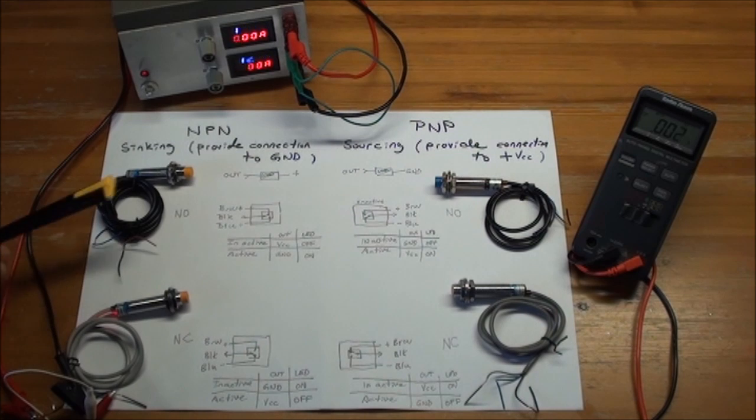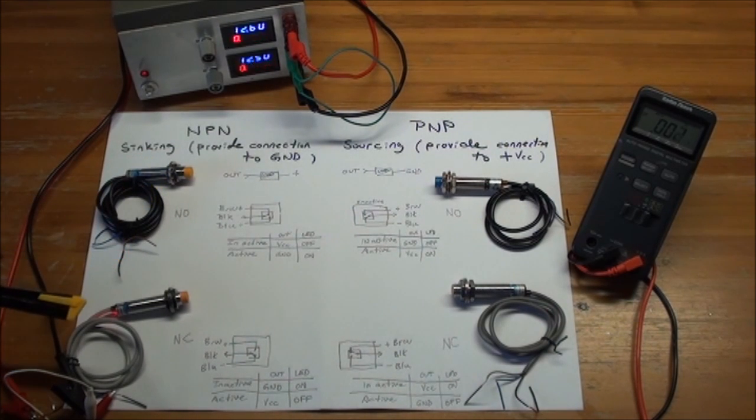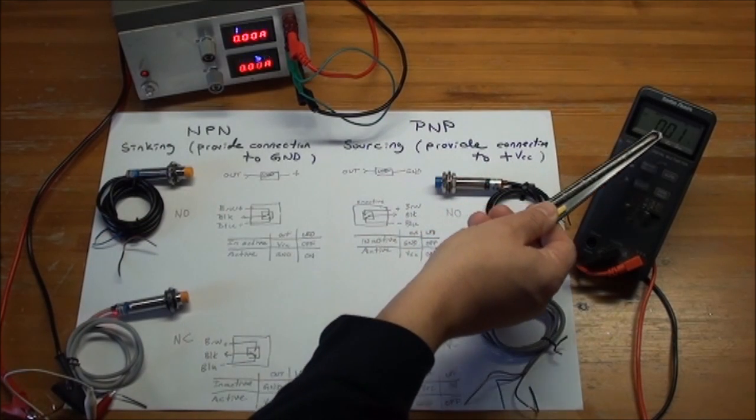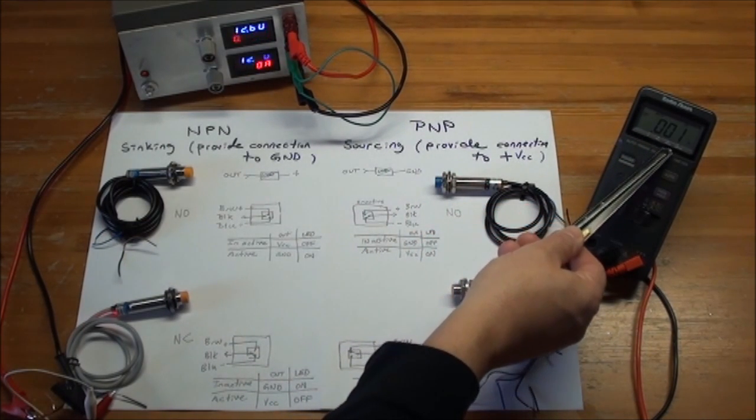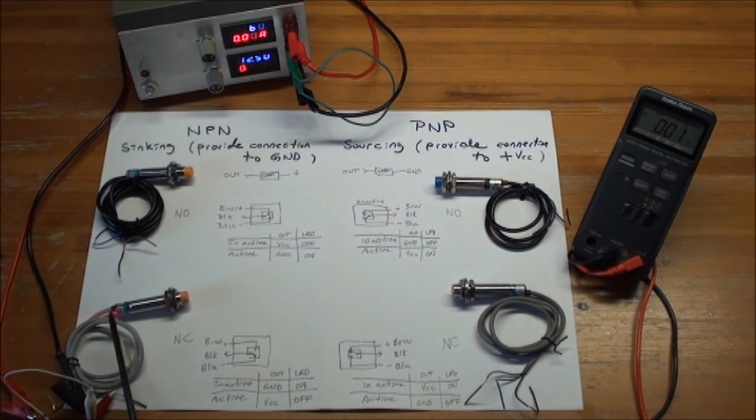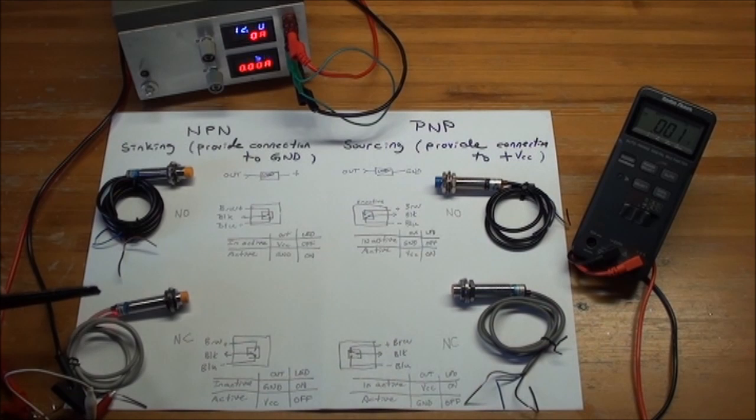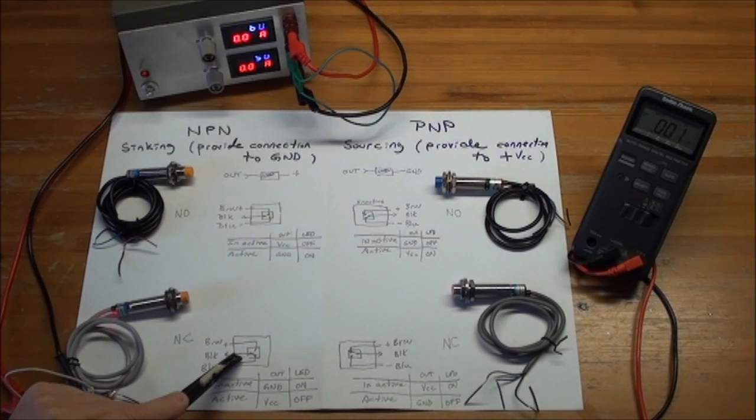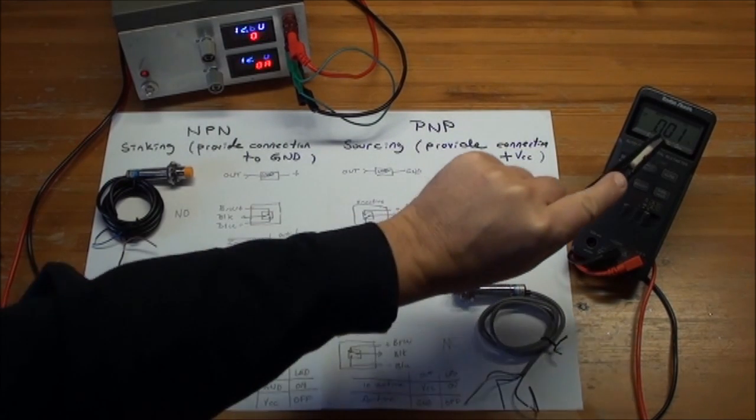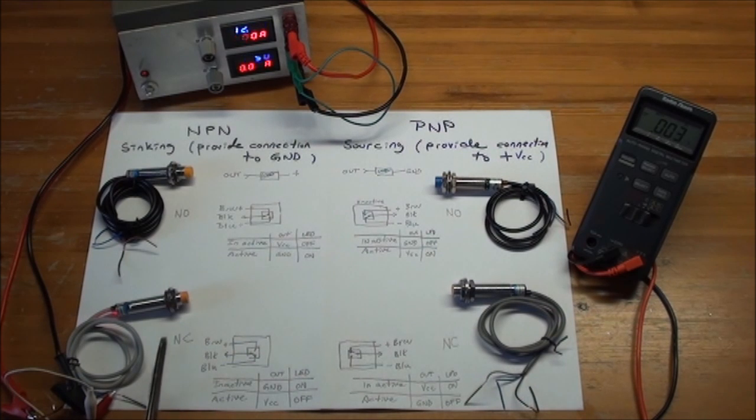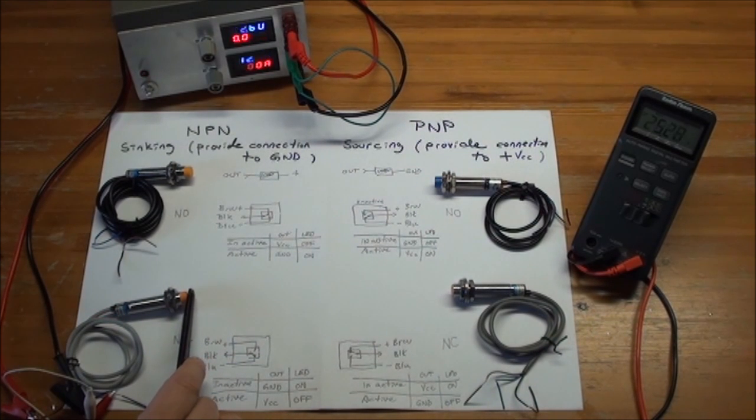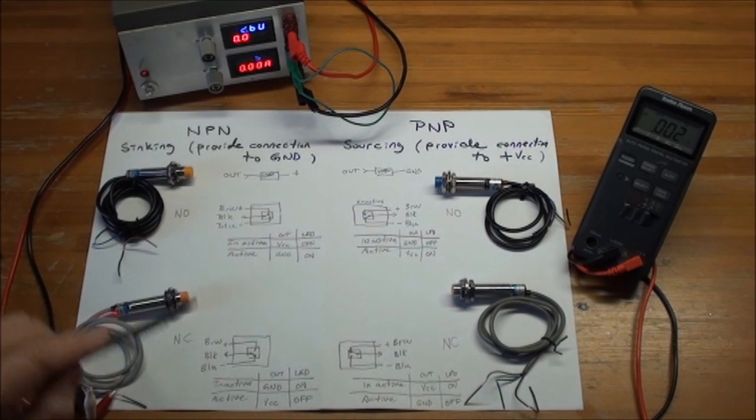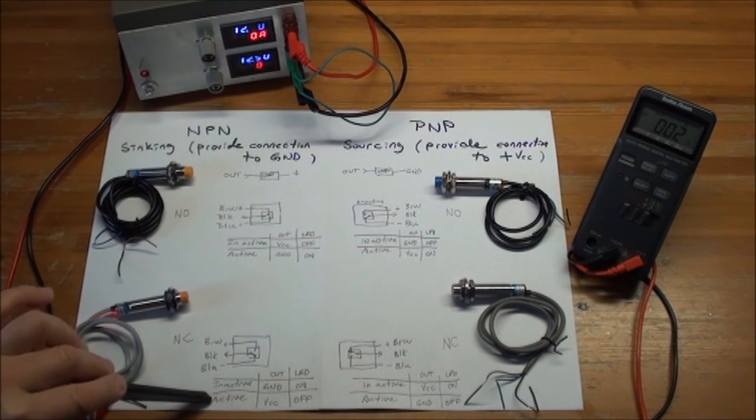And it's pretty obvious that we have the mirror image between what we saw up here. First of all, the output is not 24, it's zero. And you see the LED is on. So for the NPN normally closed, the internal diagram is that you have a connection in the inactive state between the black and the blue, which provides you ground on the output. And as soon as we activate it, you will get the 24 volts out and the LED goes out.